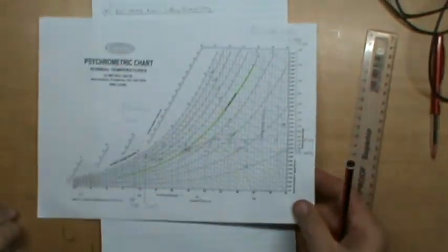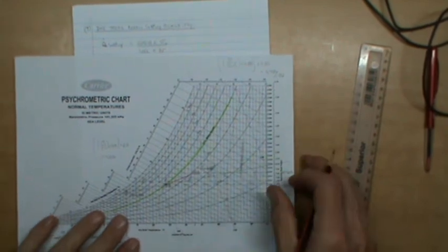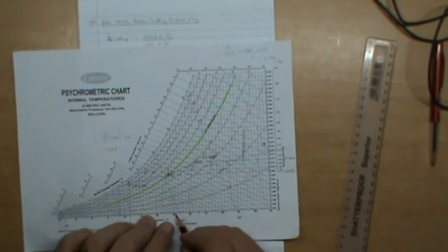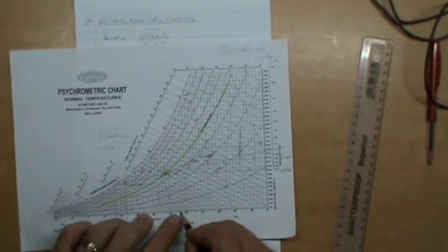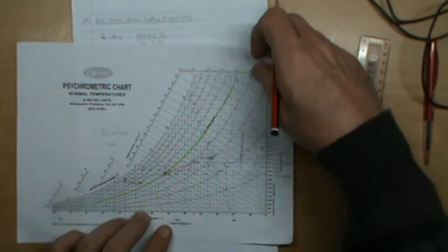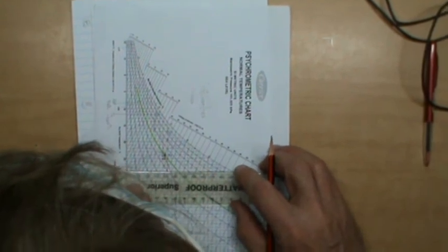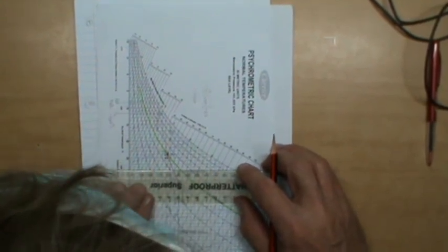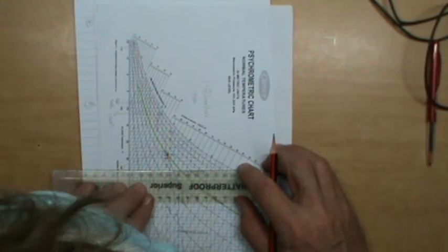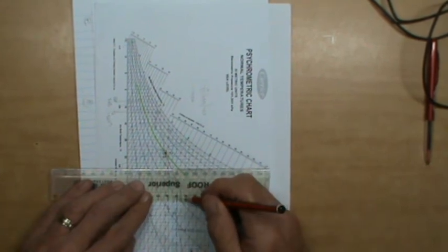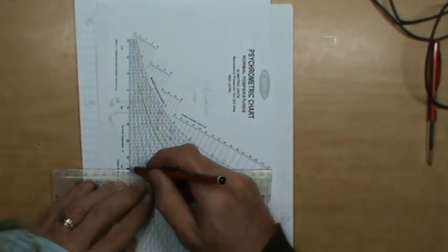And that value now we're going to plot on the psychrometric chart. There's our chart, and it is 28,476. 25, 26, 27, 28, 476, so it's about 28.5, eh? 28,476. And you're going to draw that up to cross the line that is drawn between state point 1 and state point 2. So there we go.